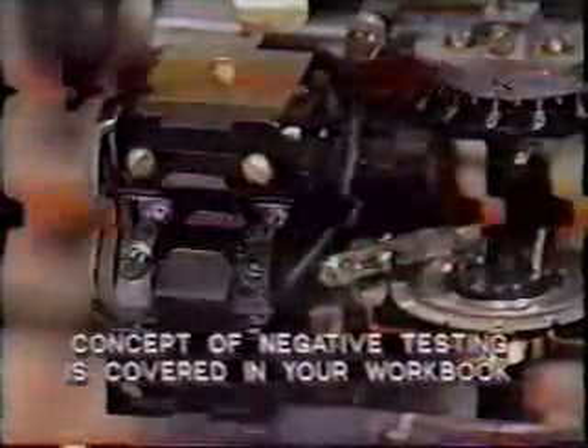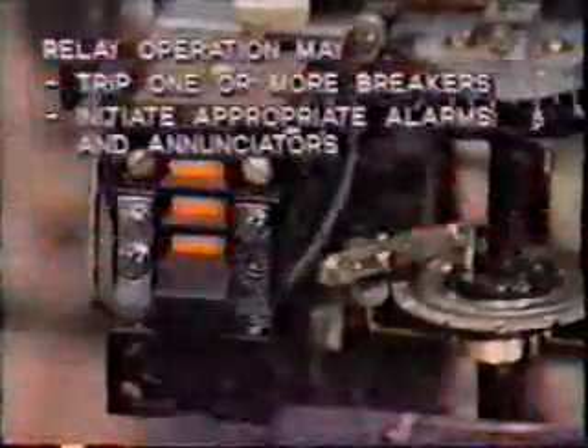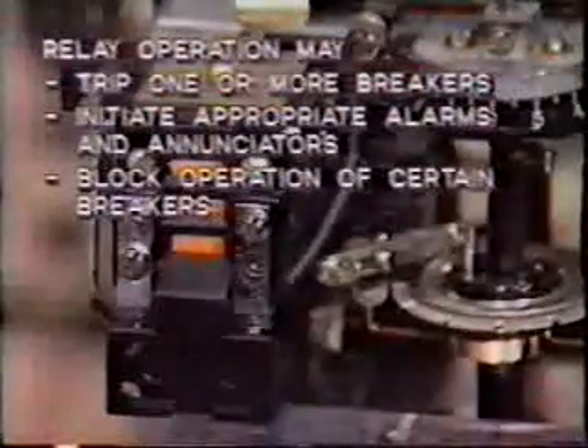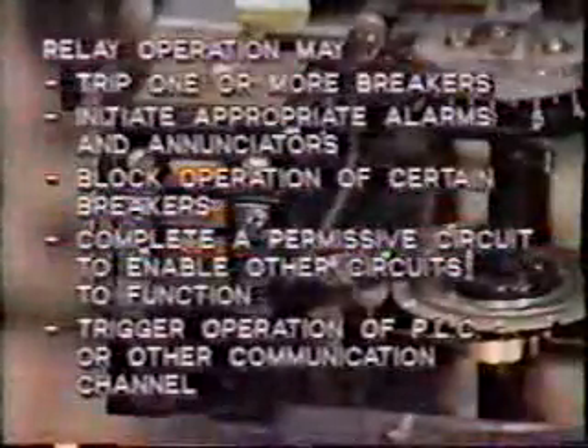After the relays have been checked out and calibrated, functional tests of the tripping circuits must be performed. The objective of function tests or operation tests is to verify that when a particular relay operates, its output produces the desired action. Typically, relay operation may trip one or more breakers, initiate appropriate alarms and annunciators, block operation of certain breakers, complete a permissive circuit so as to enable other circuits to function, or trigger operation of a power line carrier circuit or other communication channel. I'm sure that you can think of many other protection relay functions.